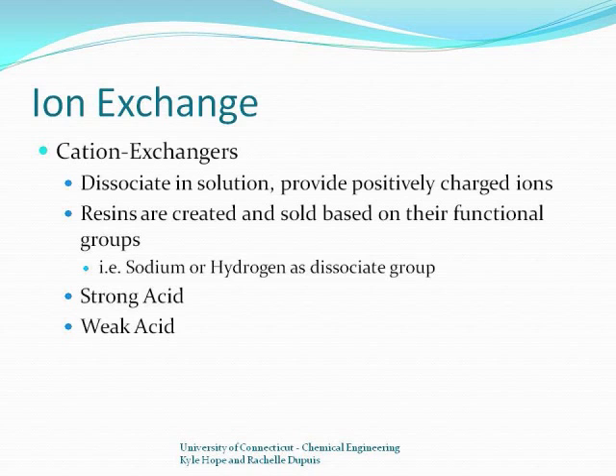Ion exchange resins can be classified into two general categories: cation and anion exchangers. Cation exchangers dissociate in solution and provide positively charged ions, which can be swapped for unwanted ions in another solution. Ion exchange resins are created and sold according to their functional group — for instance, there are resins that give sodium ions, used in most water softeners to replace hardness ions, and resins which give hydrogen ions, used to make exceptionally pure water. Cation exchange resins can be further classified as strong acid or weak acid because they mimic the behavior of those substances.